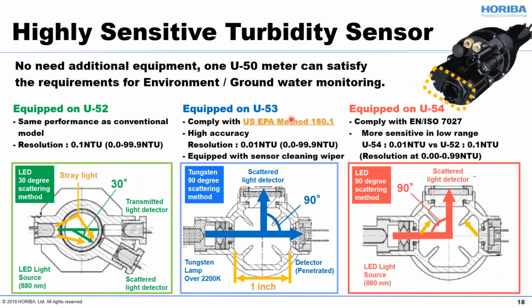This is the detail of the turbidity sensors. So we have 3 kinds of turbidity sensors like this. The conventional way is a 30-degree scattering method. It is very simple and a sufficiently effective measurement method. But if you want a more accurate value, we can supply a tungsten or LED lamp with a 90-degree scattering method. Here, the tungsten 90-degree scattering turbidity system equipped on the U-53 complies with the USA EPA method. And the LED 90-degree scattering turbidity system equipped on the U-54 complies with European regulation like the ISO series. So you can choose the model as your requirement.